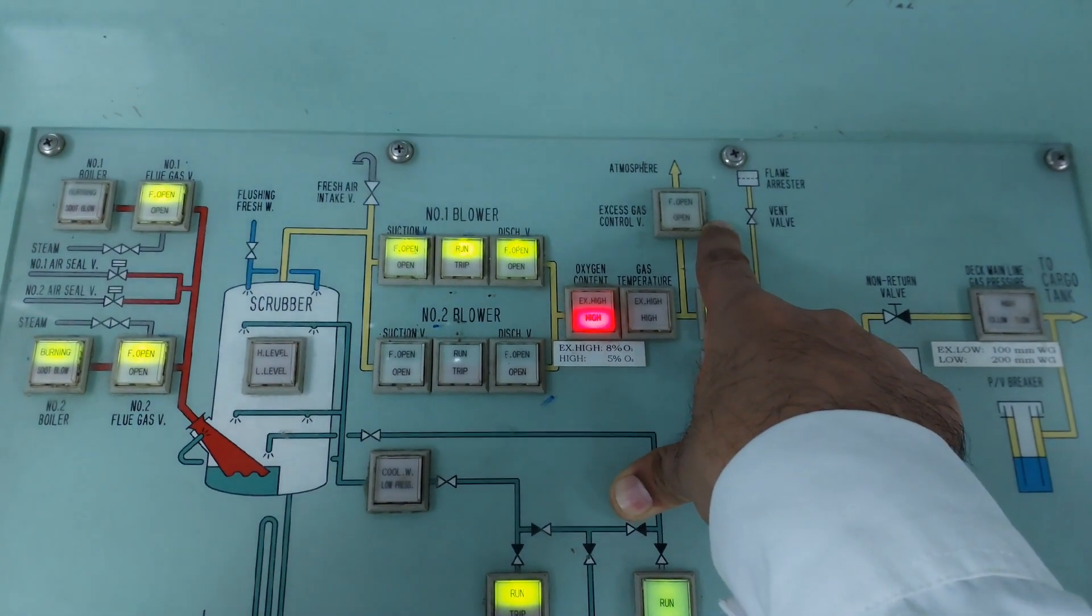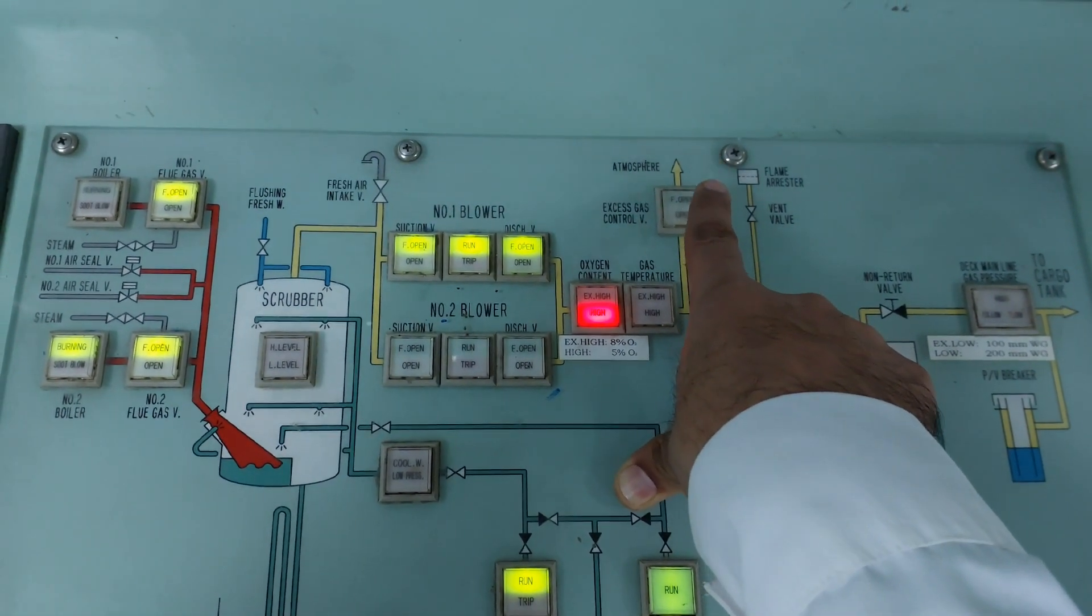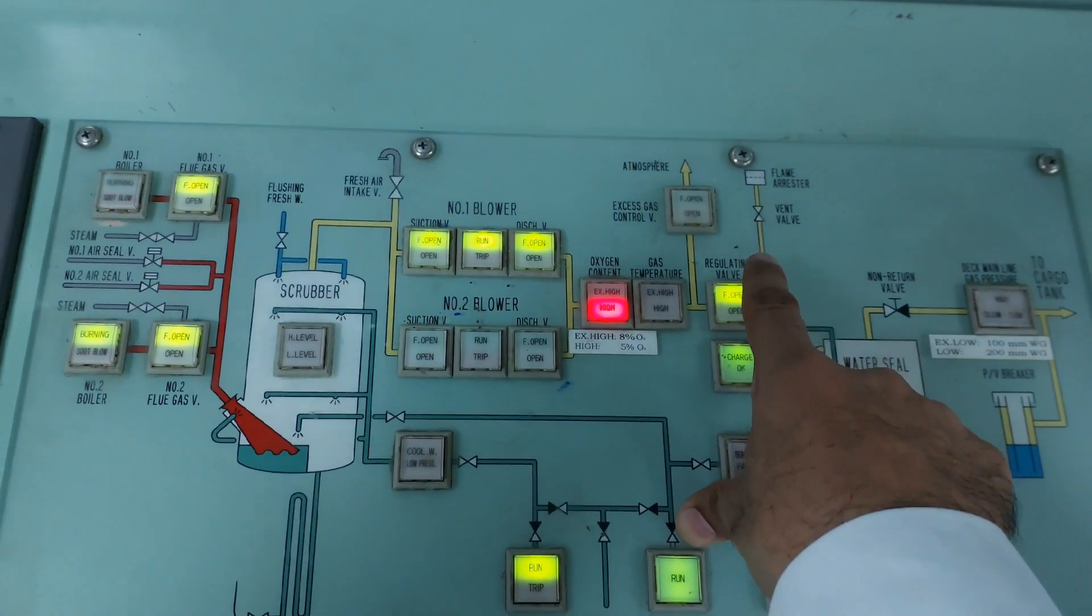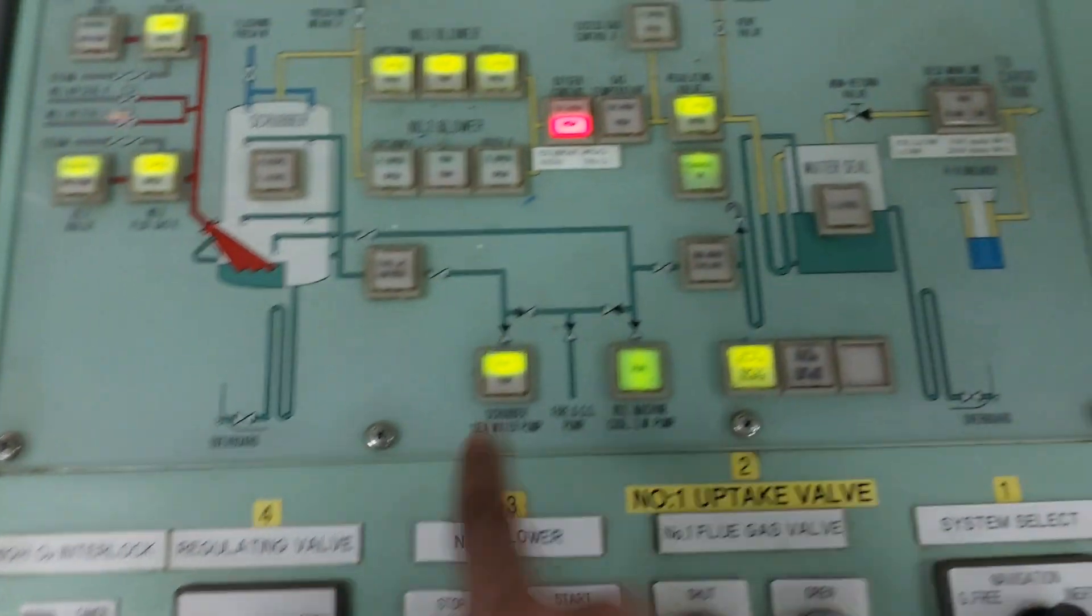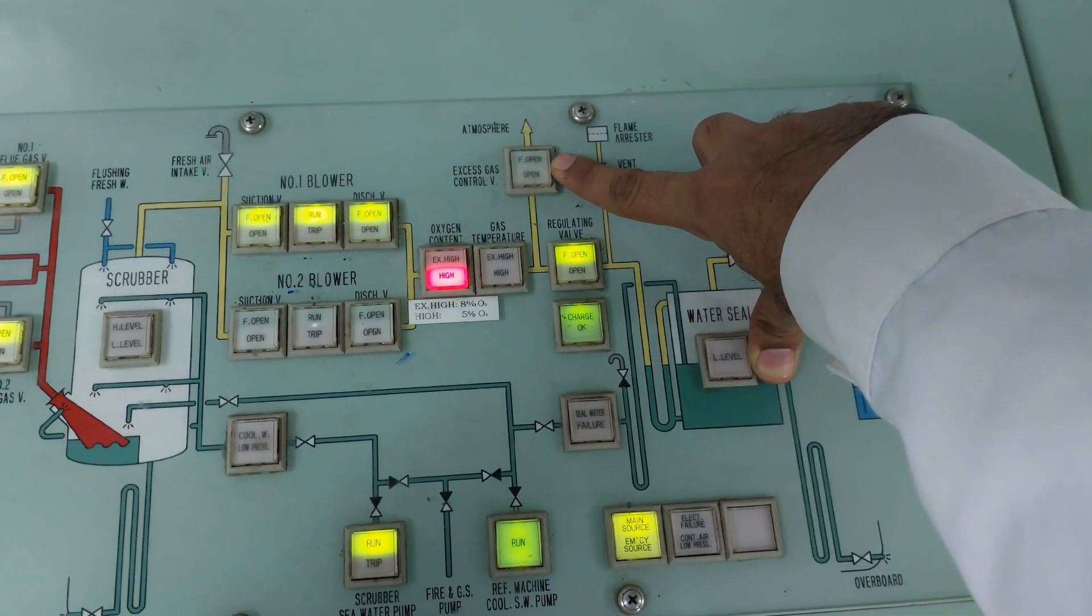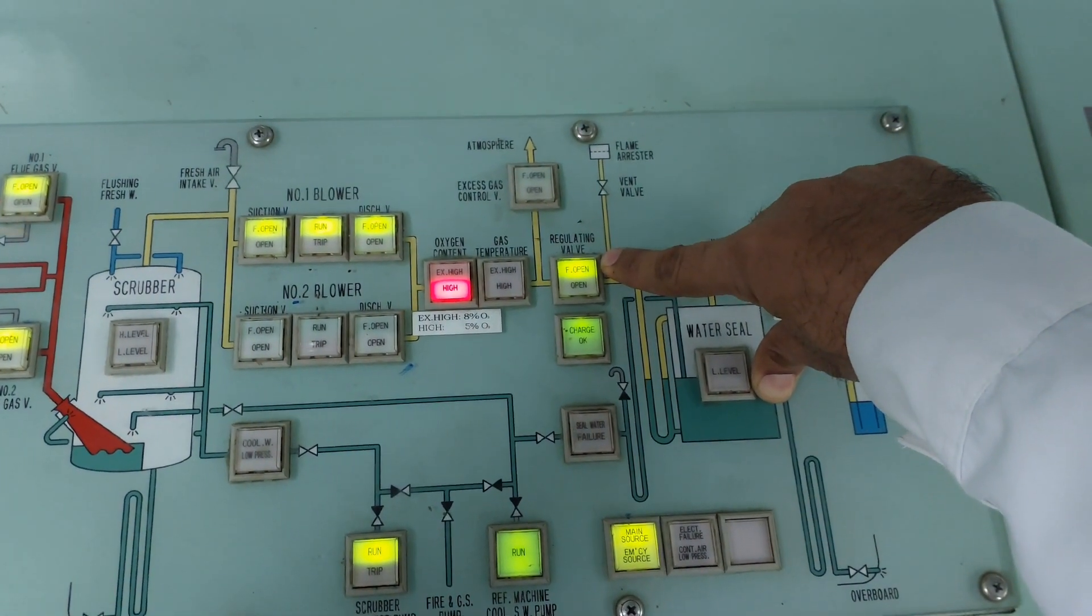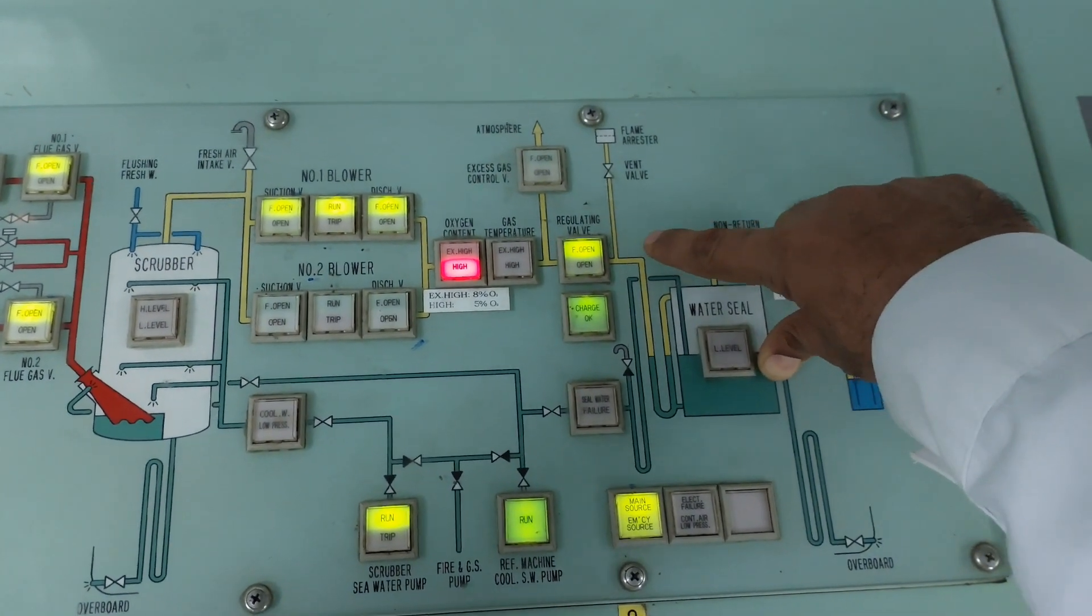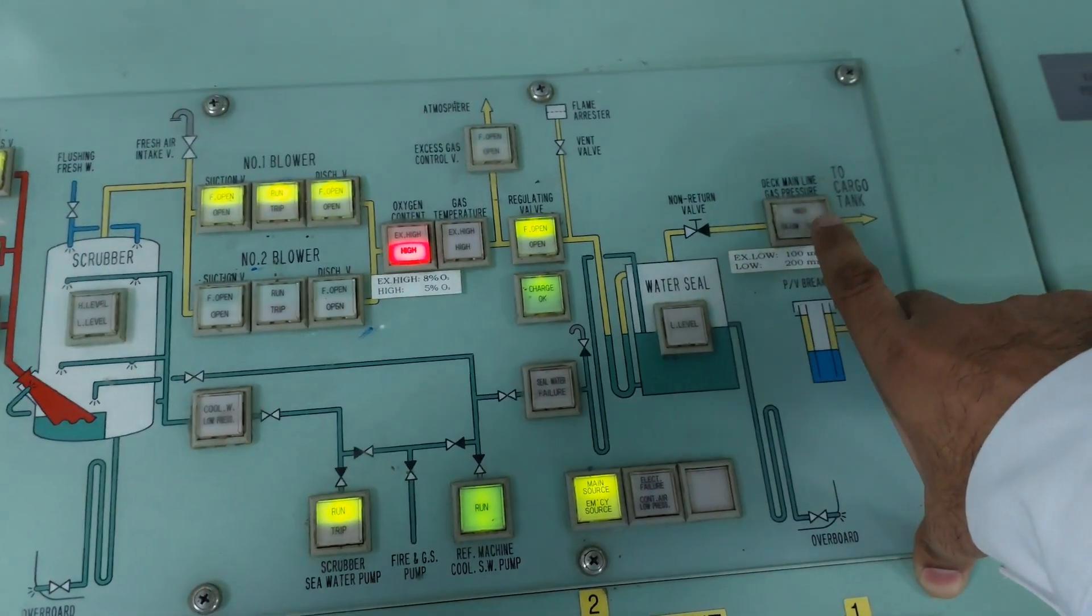There are two valves: one is this excess gas control valve. If you open this, the IG will go to atmosphere. If you close this, the IG will go to tank systems. Here you open this regulating valve. You have closed this atmosphere or excess gas control valve shut. This regulating valve is open. After that, the IG will go to deck seal. You have already opened this IG isolation valve and non-return valve.